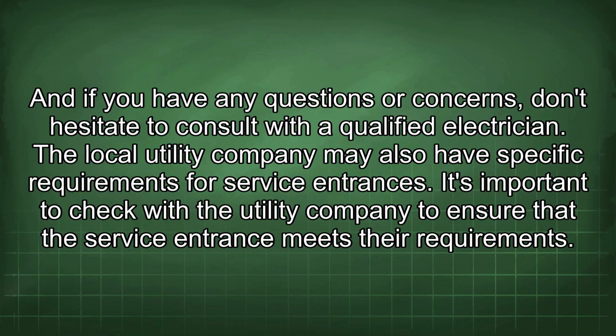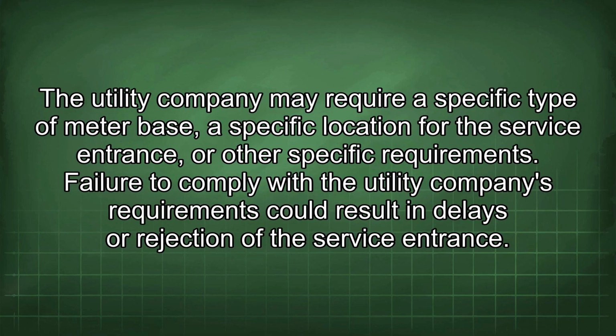The local utility company may also have specific requirements for service entrances. It's important to check with the utility company to ensure that the service entrance meets their requirements. The utility company may require a specific type of meter base, a specific location for the service entrance, or other specific requirements. Failure to comply with the utility company's requirements could result in delays or rejection of the service entrance.